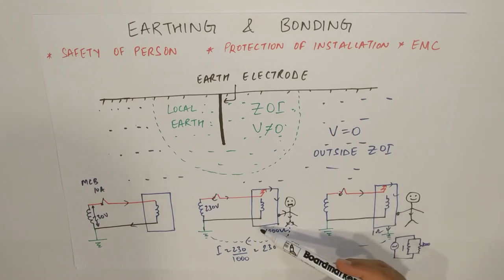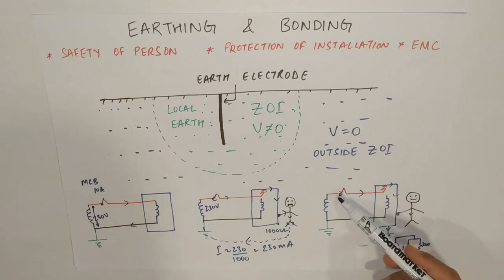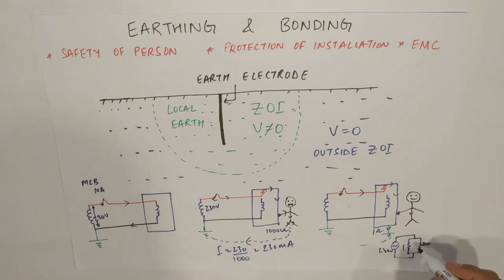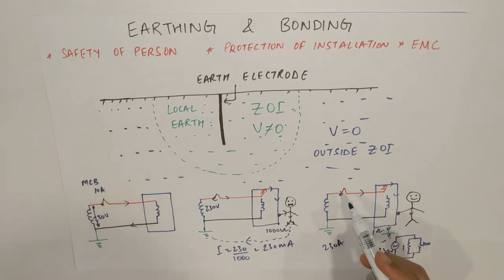Let us go ahead further. Suppose, you provide earthing to this equipment frame through an electrode and it is having a resistance of 1 ohm. Now, as you turn on this MCB and there is a fault, then what will happen? The current will flow. Some current will flow through human body also. Because it is not infinite. It is some 1000 ohms. And this is 1 ohm. So, your model will become like this. This is 230 volts. 1 ohm and 1000 ohm in parallel. Most of the current will flow through this low resistance path. And the current flowing will be having a very high value of around 230 amps. Which will cause the tripping of this MCB. So, that means you have protected your installation also by tripping within time. And also your human, which is not getting exposed to current for a longer duration.